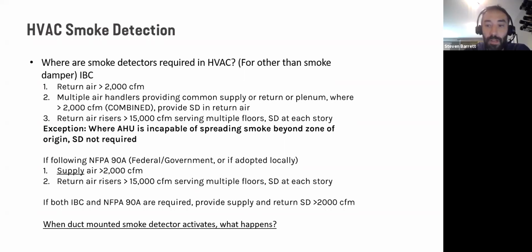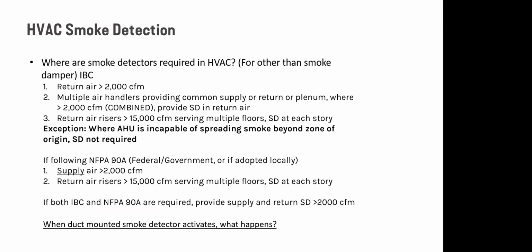So next poll question, when a duct-mounted smoke detector in an air handling unit activates, what happens? You can initiate the general fire alarm, shut down fans of the respective AHU, close all fire and smoke dampers associated with the air handling unit, or all of the above.